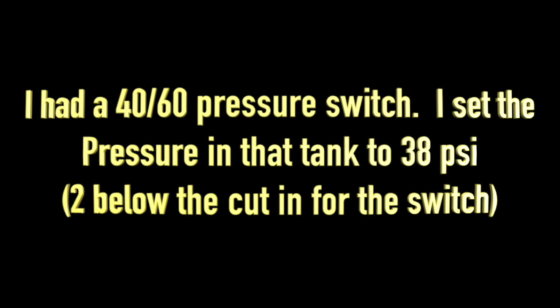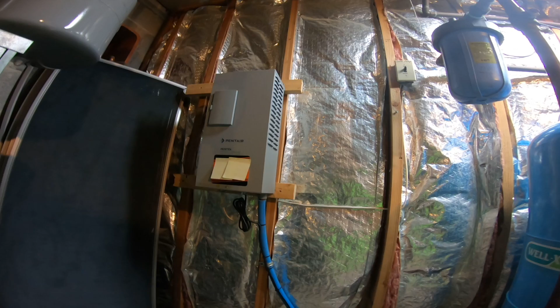They also set up the motor incorrectly. You're supposed to set the amps of the motor. In this particular case, I looked it up. The motor that we have on the pump should have been set at like 7.6, and they set it to 8.0. So again, they could have overloaded the motor. So they did that wrong. They set the pressure wrong in this. This is in the wrong place. This is parallel. And I'm not in love with the fact that this is so close to the boiler.